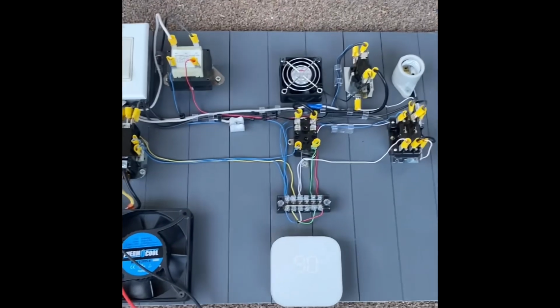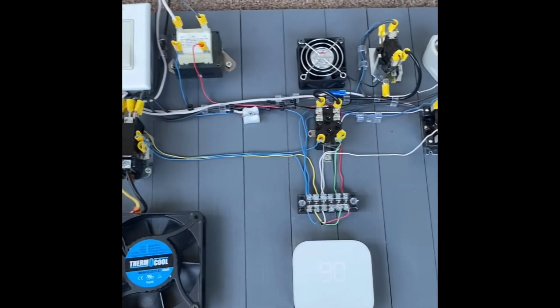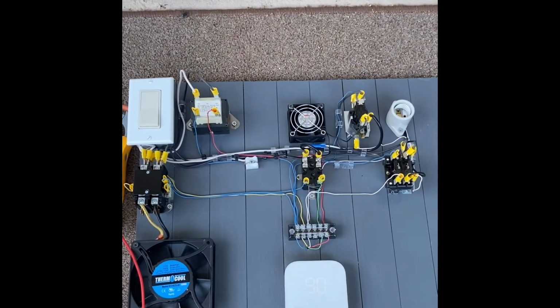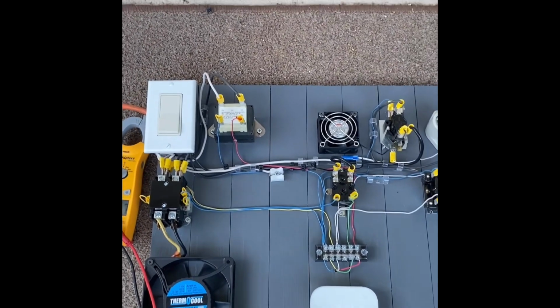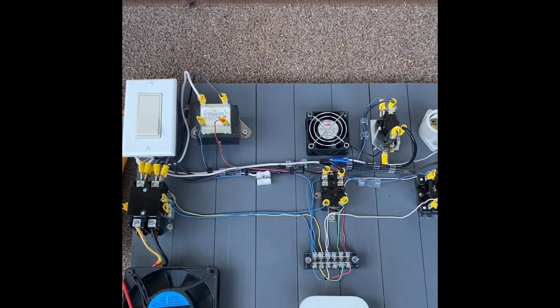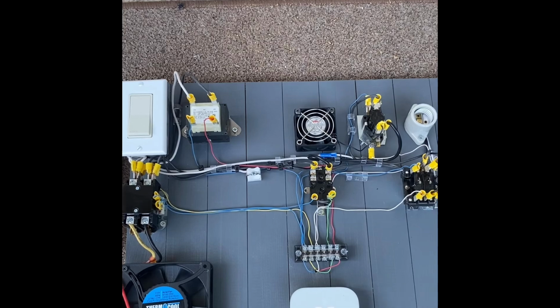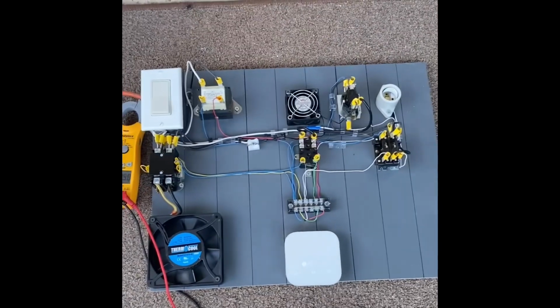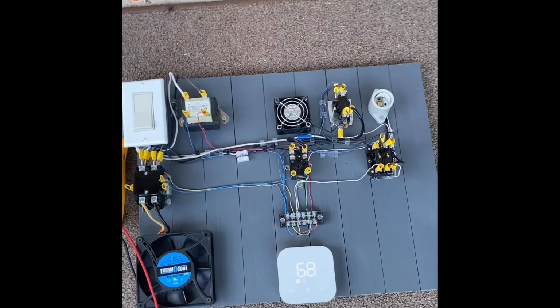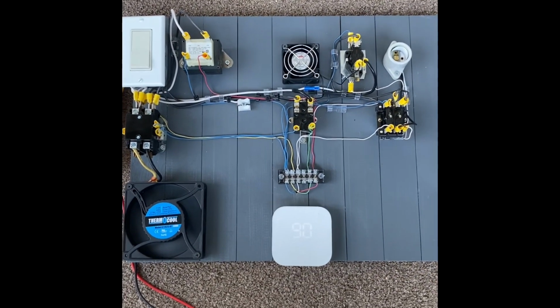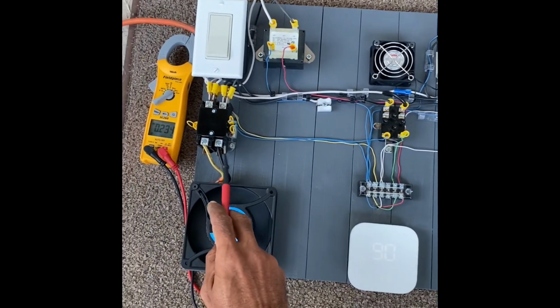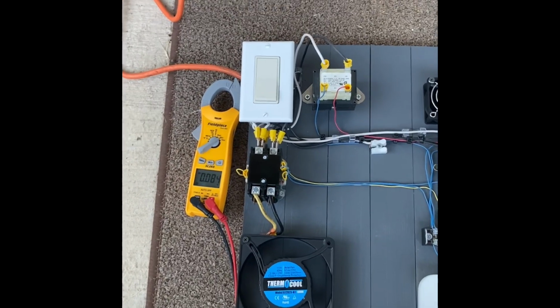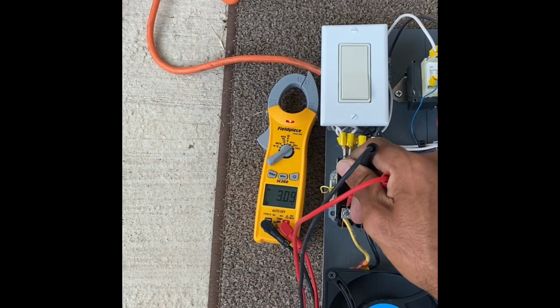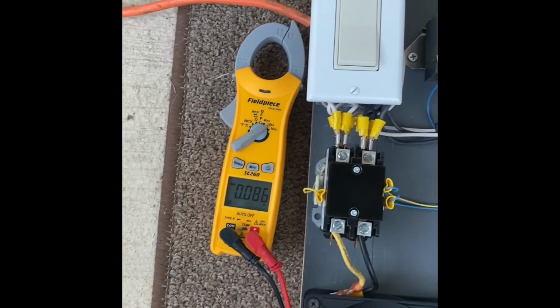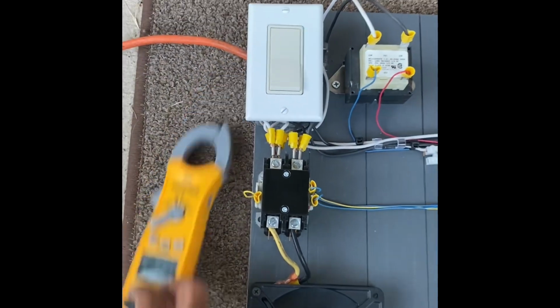So now we're gonna test. We're gonna change the set point, and we're gonna be checking amperage and some of the other things. So now it is off, right? It's on cooling. Now we're gonna lower the set point. Let's leave it on 68. Okay, so now the unit is working on cooling. We're gonna check power coming out of the contactor, even though we know the condenser motor is running. So we're gonna put one lead on one side and another lead on the other side, and we have 120 volts.